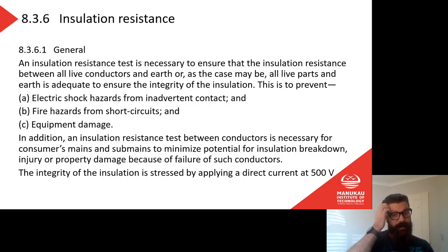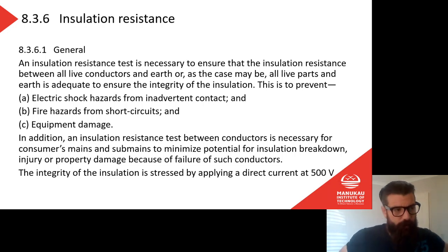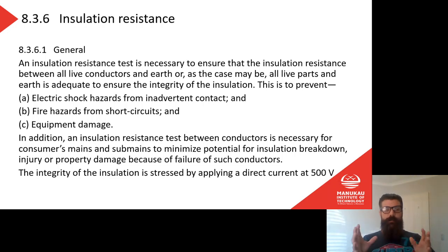In addition, an insulation resistance test between conductors is necessary for consumers' mains and submains to minimize potential for insulation breakdown, injury, or property damage because of a failure of such conductors. The integrity of the insulation is stressed by applying a direct current at 500 volts. Right, what does all that mean? Okay, insulation resistance might be the most difficult test for you to understand. Let's see if we can pull it off.